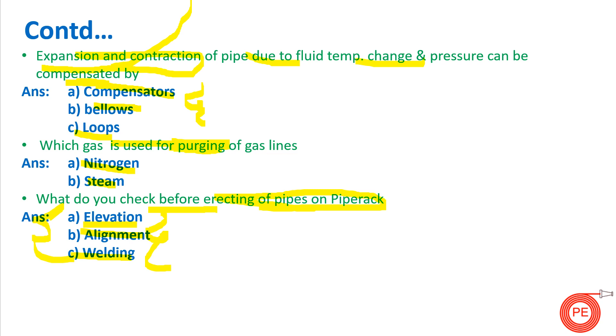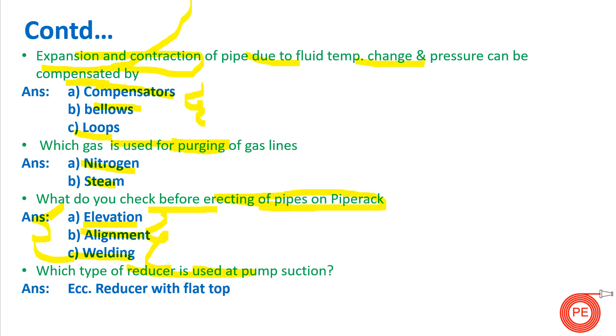The next question is: which type of reducer is used at pump suction? An eccentric reducer with flat top is used at pump suction. The eccentric reducer is used so that cavitation inside the pump can be prevented — otherwise cavitation will occur and harm the functioning of the pump.